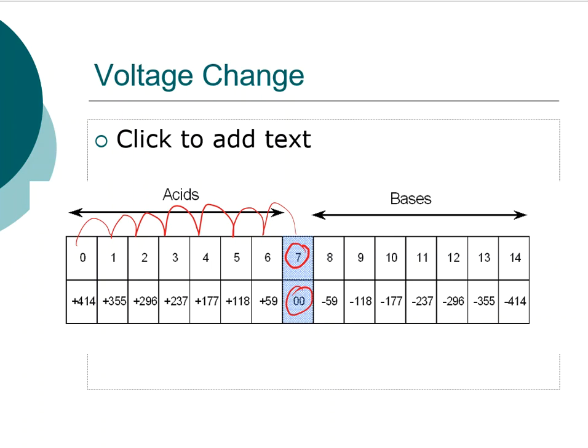So what happens here is that this is going to be 59 millivolts. And then another pH value, when we go to pH of 5, that's another 59. We go to another pH of 4, that's another 59. Then we go to 3 and 2 and 1 and pH of 0 and on and on. Every time we go into a different pH whole number, 6, 5, 4, 3, 2, 1, we gain another 59 millivolts in the electron flow. And this meter is looking at the millivolts that this thing is starting to create, and it's looking at that readout, and it's corresponding that to a pH value that is on this scale.